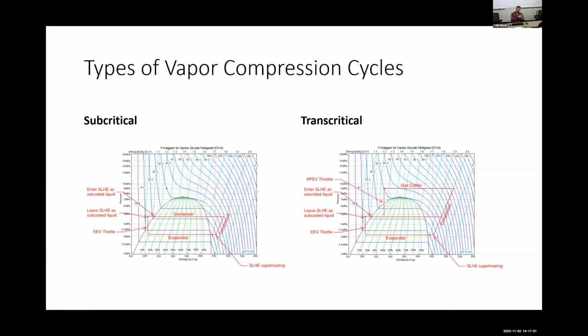So when you have a chiller or a heat pump and that condenser, you're actually heating up a fluid while you're condensing this refrigerant. There's no temperature change on the refrigerant side because it's on the saturation curve, and that means that you don't really care about the entering temperature. You mainly care about the leaving temperature, and that heat exchanger is designed based on the leaving temperature.